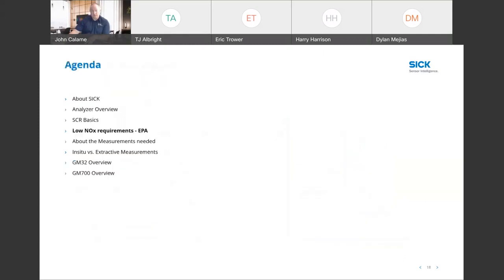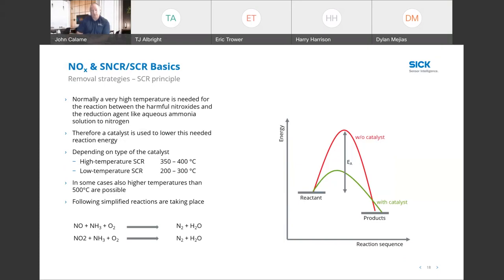Yeah, and for this, this is Dylan. For that low slip, you're looking at probably sub 5 ppm, really sub 2 ppm of ammonia for an optimized conversion. So you do need a device which is going to be very accurate on the low end. A lot of devices out there are good for 0 to 25 ppm for ammonia, but when you look at high accuracy at that low measurement, you're going to be leaning more towards something like a TDLS, which I think John's going to be talking about here in a bit.